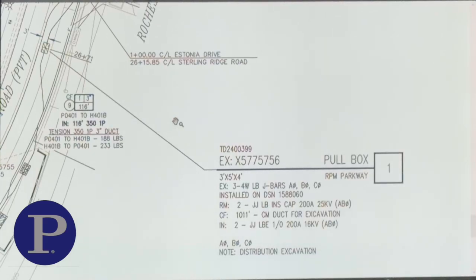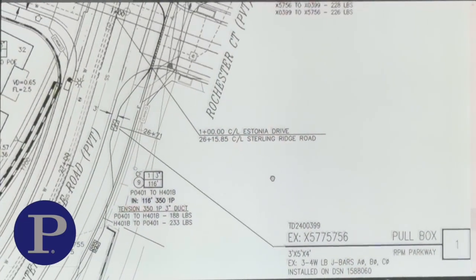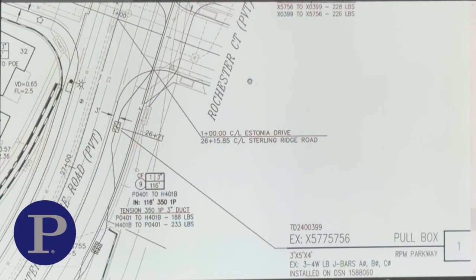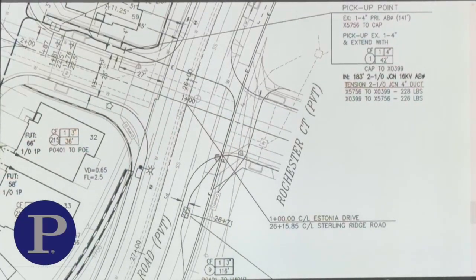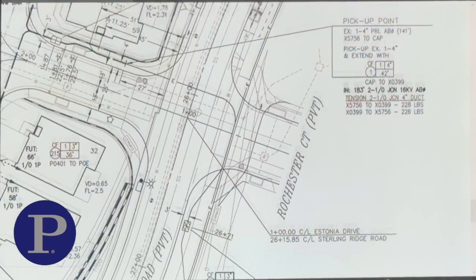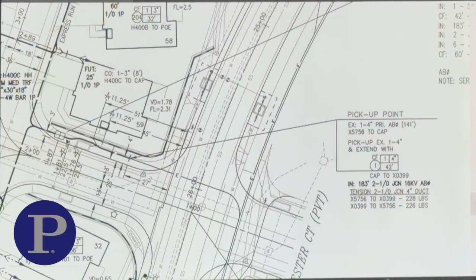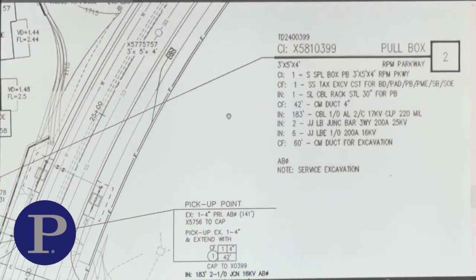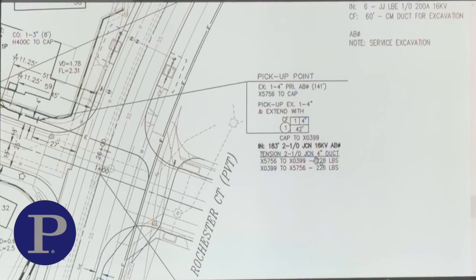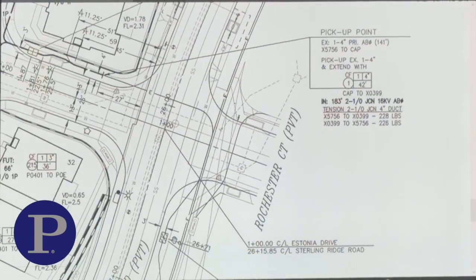So looking at this portion of the print, we're going to start with the existing structure. This is the structure number right here. We know that it's a pull box. This gives us all the information. This is where it all starts. From here, you can see that we're coming around. If we follow this line, we're going to be pulling it to this other pull box right here. And then if you follow what's pointing at that, this is the description of that new pull box that we're installing. We know, based off of the single line, if we start at the existing structure to the new structure, and this gives us all the information on what we're pulling.